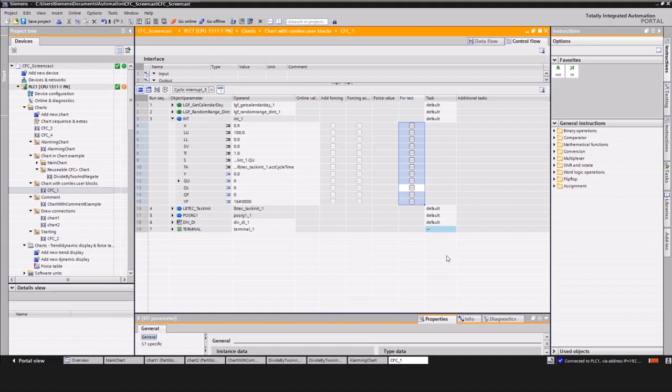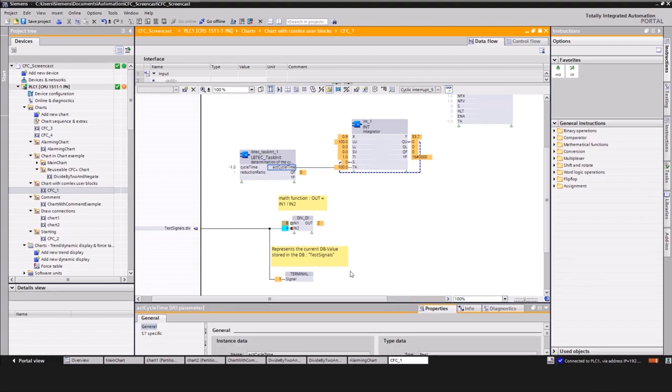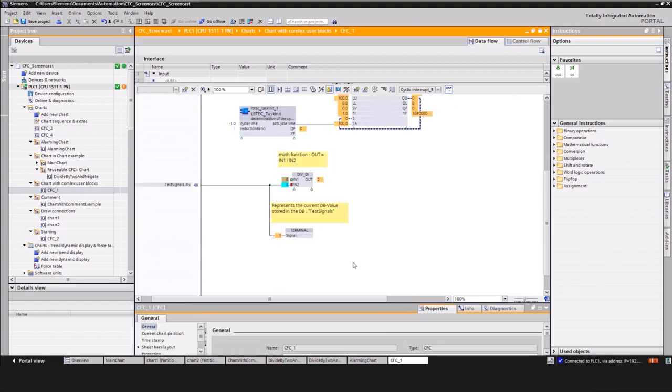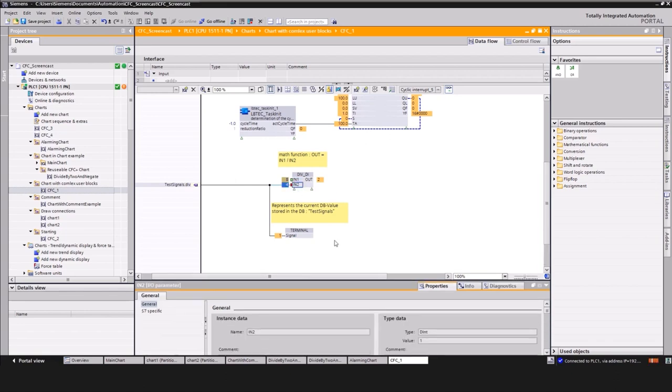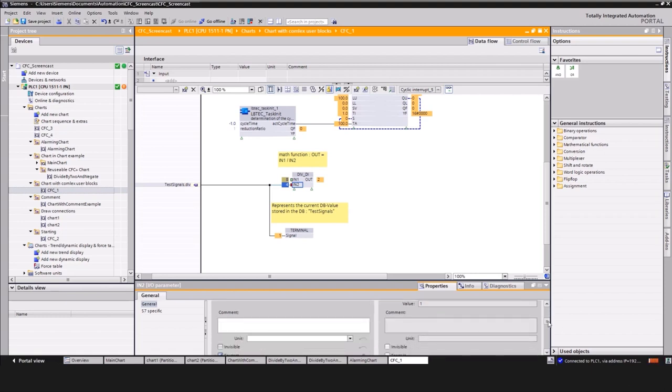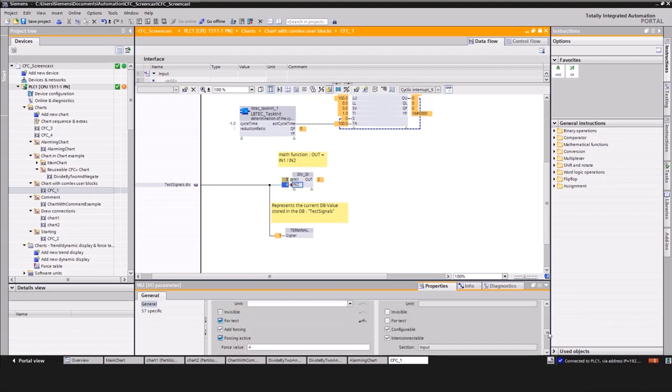The testing phase is not limited to only observing values. By setting the option to force values, the user can even force inputs to blocks that have a connection. But note, the activation of forcing requires a software delta download.